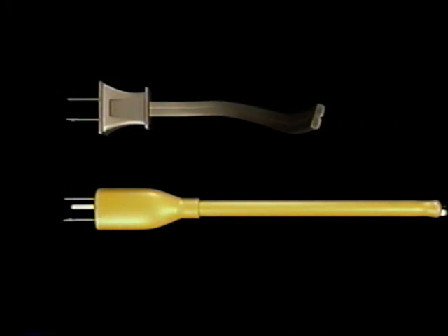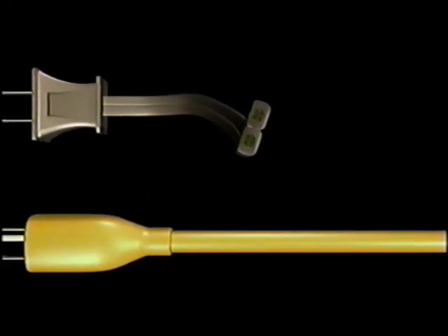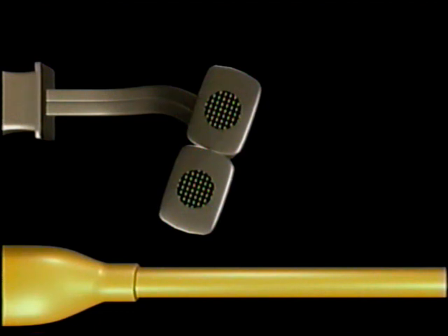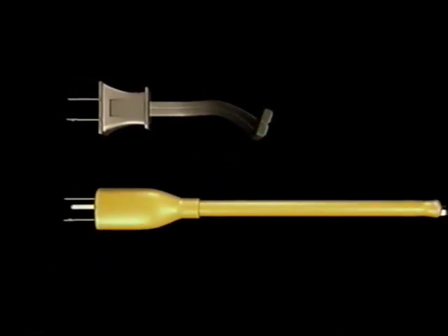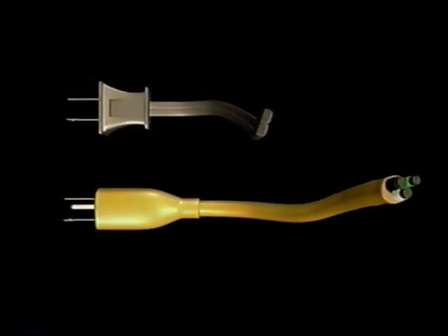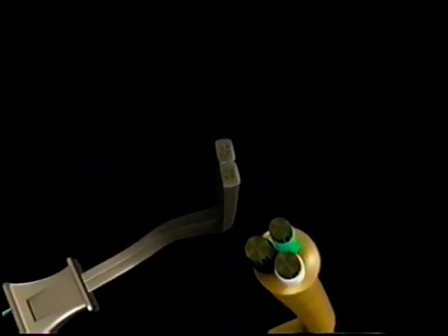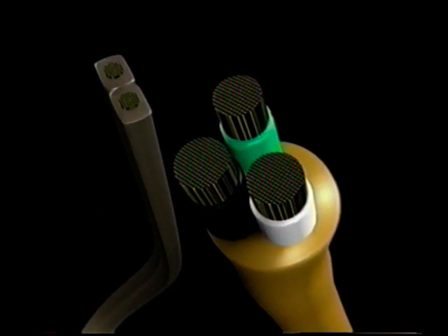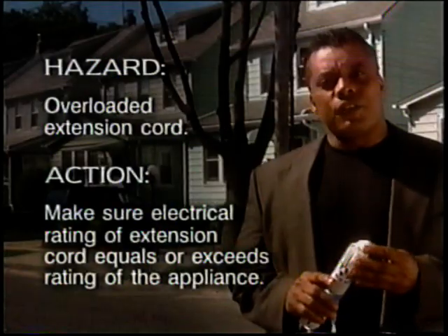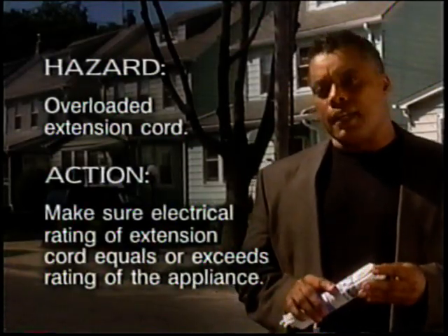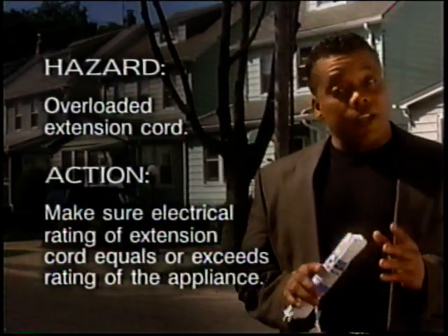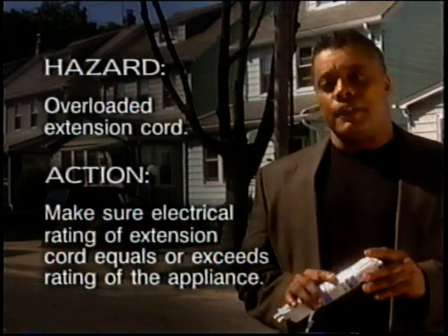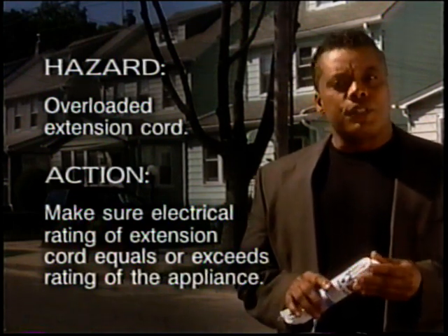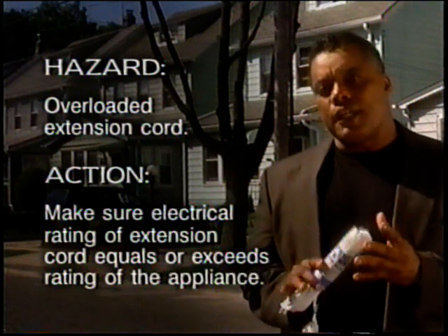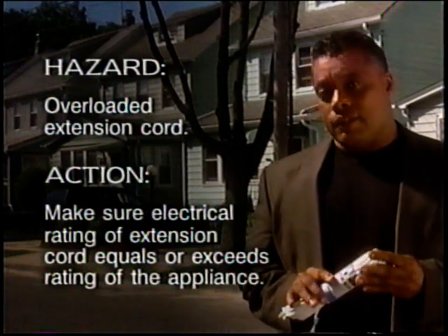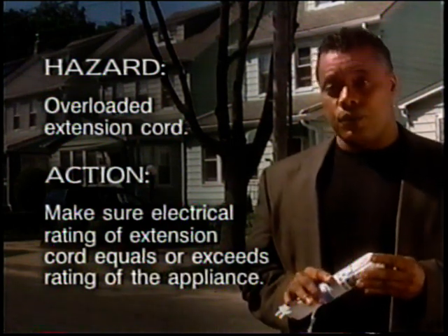A light extension cord such as an 18 gauge cannot safely handle the amount of power required by, for example, a 1400 watt portable heater. Heavier gauge extension cords of reasonable length can safely carry bigger loads. To be safe, check the electrical rating on both the appliance and the extension cord. Never exceed the rating on the cord. It's important to remember that fuses and circuit breakers are designed to protect the house wiring only. They won't protect an overloaded extension cord from overheating.